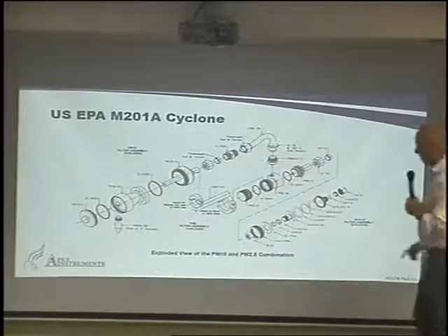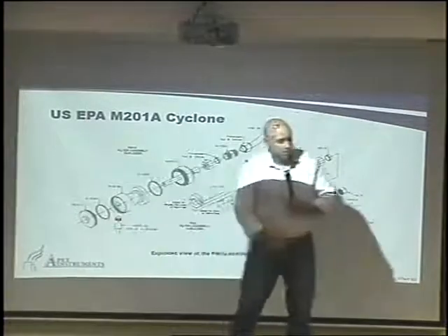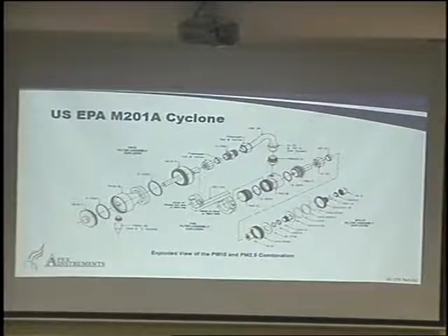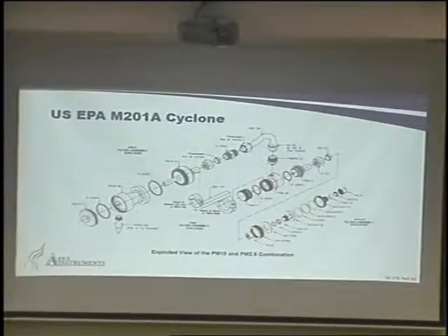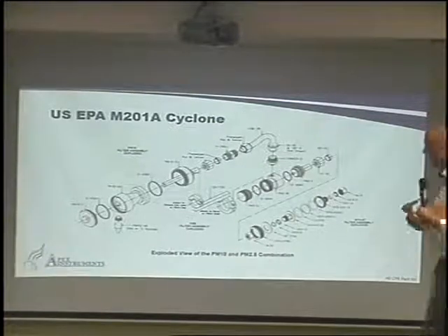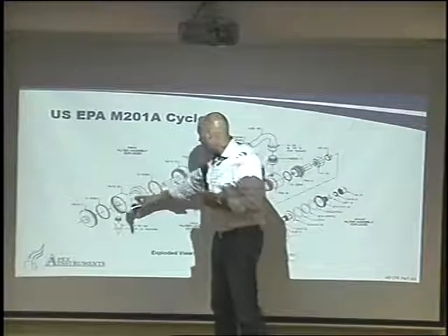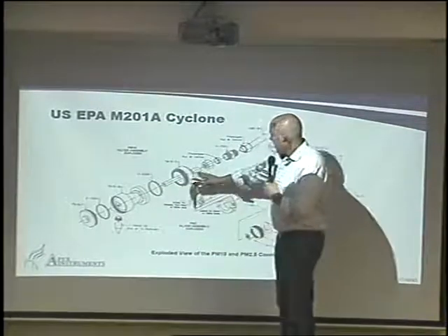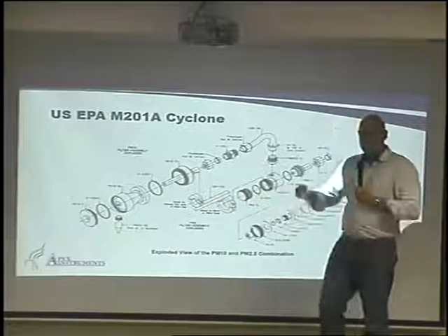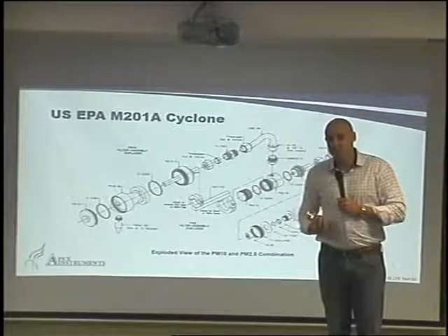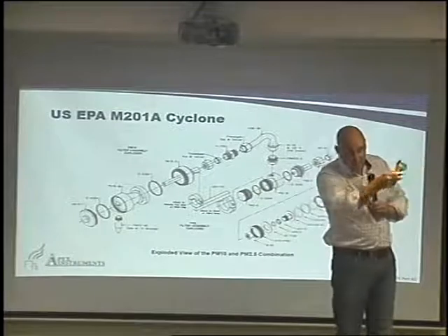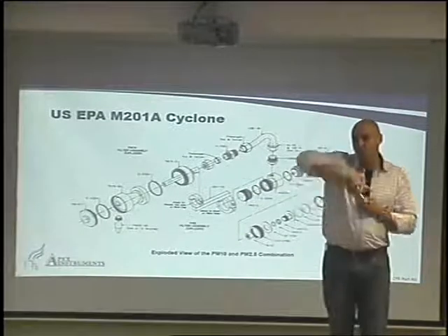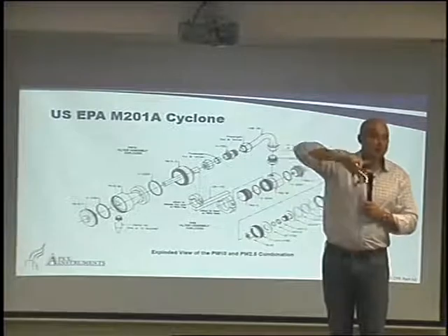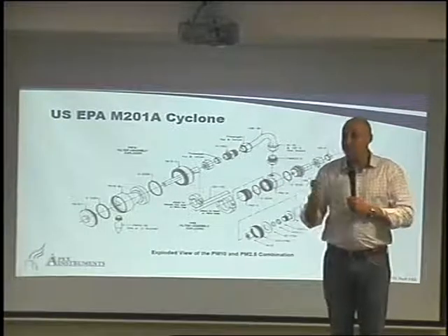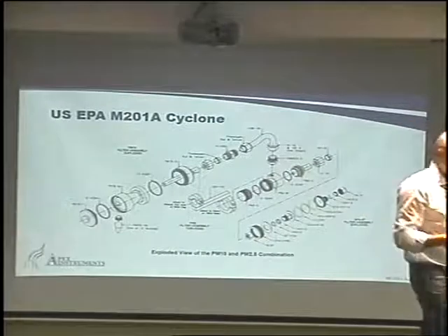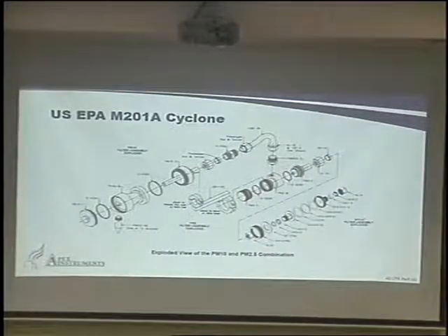But basically, that guy there is our front plate on the front. We have an O-ring inside that creates a seal for us. Here we have our PM10 cyclone coming through, our nozzle size, and again, that button hook nozzle is specific to this design. It's the same as the design on the nozzles for optimum flow to allow the dust to flow correctly to the next stage of the cyclone to collect the particulate matter correctly.